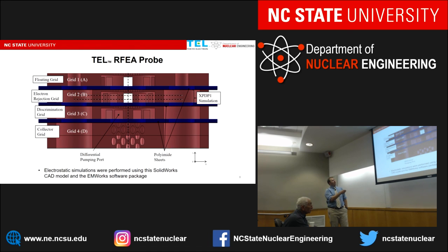But you can see I've labeled all the different grids: floating, electron rejection, discrimination, then collector. And I refer to it as a collector grid because we added these holes here in the bottom that are chevroned, so you'll collect every ion that passes through. We also have these ports here for differential pumping, and then we have polyimide insulators in between each of the grids to provide electric isolation. And then I also have a couple of lines here, which in upcoming slides you're going to see I ran SolidWorks using EMWorks to look at the electric field across these dashed lines. And then I also mentioned for some future work that we'll discuss is XPDP1 simulations were done between those two grids.